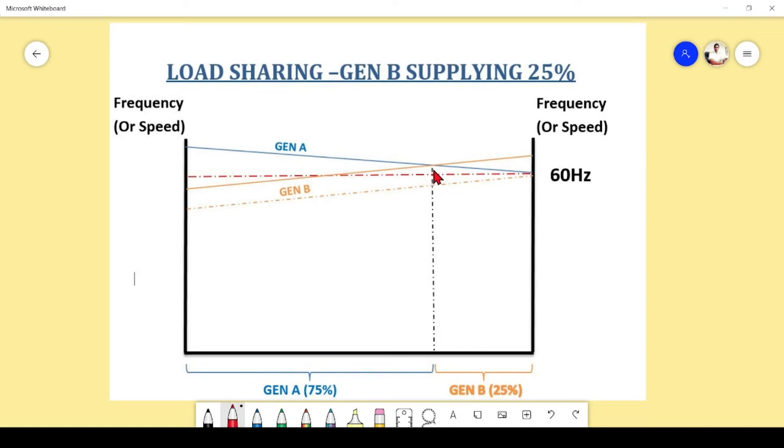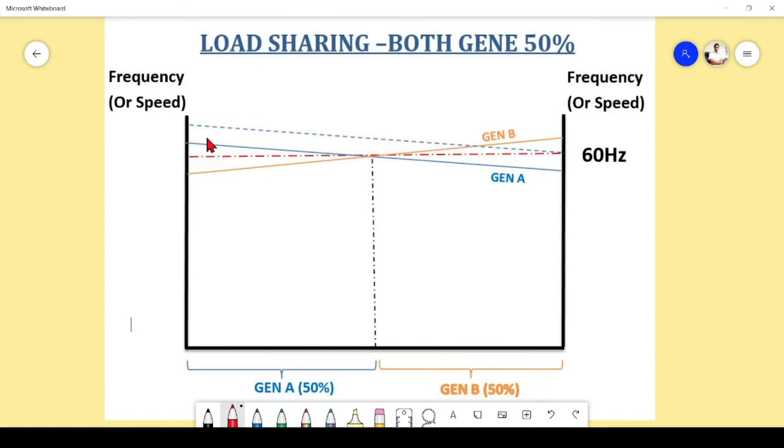Now we have to take down the speed of generator A. In this diagram we can see that we have lowered generator A speed, so the crossing point came to here at center. Both generators are sharing equally, 50 percent load, and the system frequency is remaining 60 hertz. So by adjusting the speed of both generators, we can vary the operating point of which generator is taking how much percentage of the load.